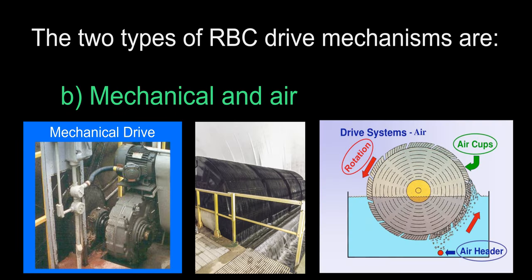The answer is B, mechanical and air. RBC stands for Rotating Biological Contactor, which is a biological fixed film treatment process used in the secondary treatment of wastewater. It consists of a series of closely spaced parallel discs mounted on a rotating shaft supported just above the surface of the wastewater. Microorganisms grow on the surface of the discs where biological degradation of the wastewater pollutants takes place. Most systems nowadays use a mechanical drive to rotate the media; however, some use a combination of both. Air can be useful to help with the sloughing process, which is when the biofilm falls off the media, and is necessary when wasting must be increased.